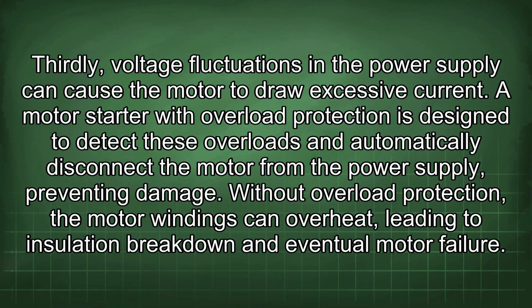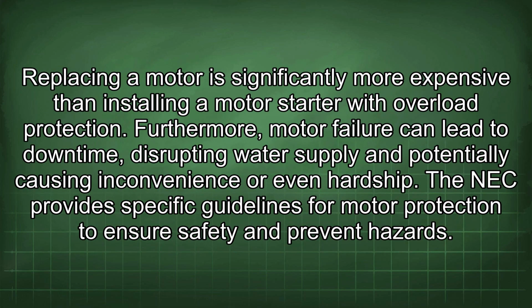A motor starter with overload protection is designed to detect these overloads and automatically disconnect the motor from the power supply, preventing damage. Without overload protection, the motor windings can overheat, leading to insulation breakdown and eventual motor failure. Replacing a motor is significantly more expensive than installing a motor starter with overload protection. Furthermore, motor failure can lead to downtime, disrupting water supply and potentially causing inconvenience or even hardship.